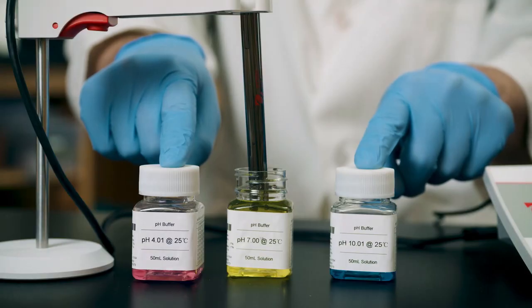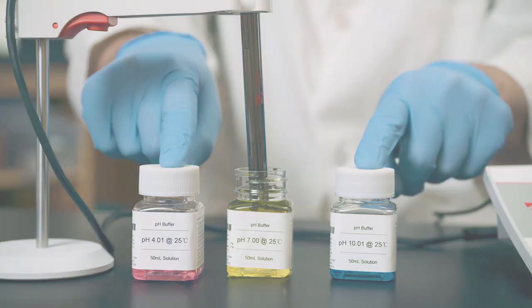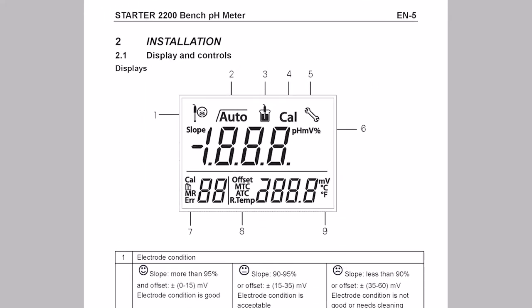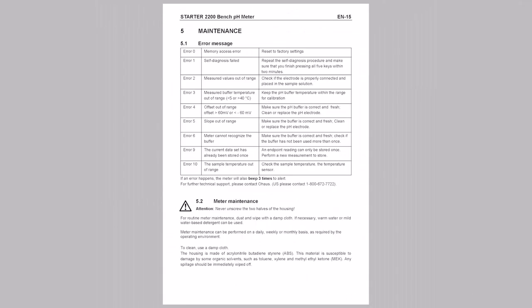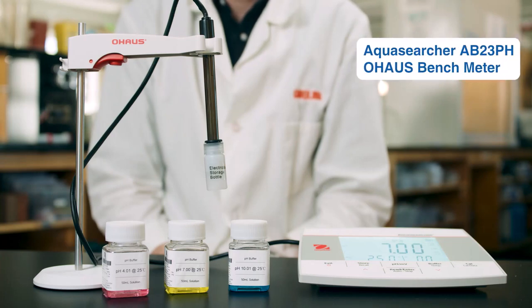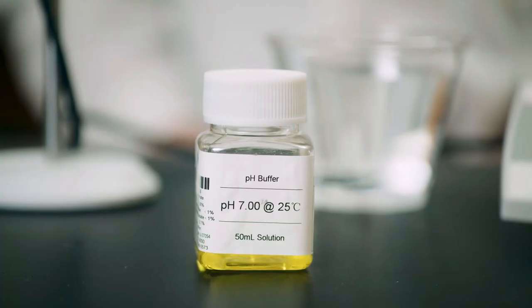Calibration methods vary between models, and the manufacturer's manual should be referred to for the model of bench meter being used. As an example, we will demonstrate how to calibrate the AquaSearcher AB23pH OHAUS bench meter, a standard pH bench meter. To calibrate, you will need the bench meter with pH electrode, distilled water, and a buffer solution. This meter uses either a 1-point or 2-point calibration. In this video, we will show you a 1-point calibration. We will use a pH 7.0 buffer solution.